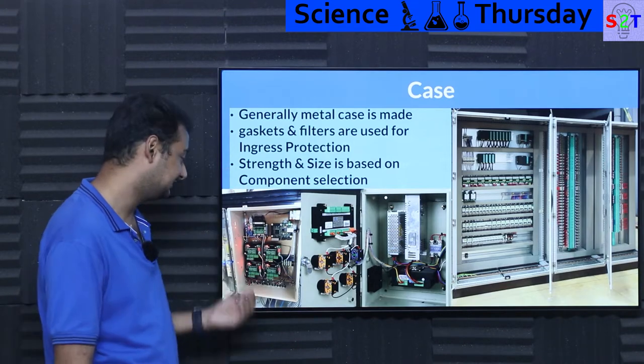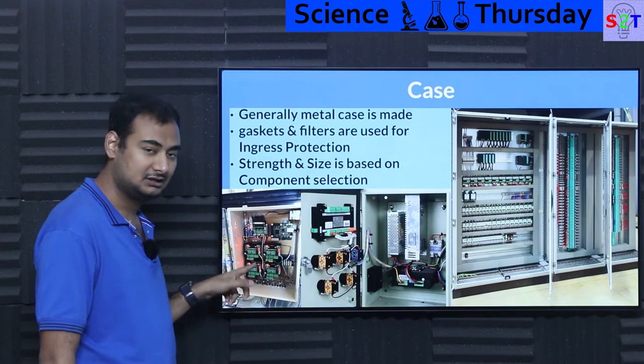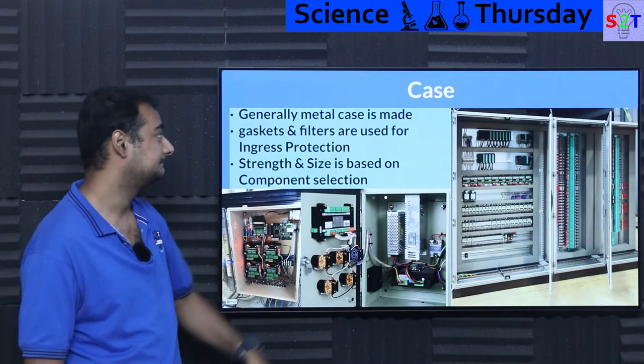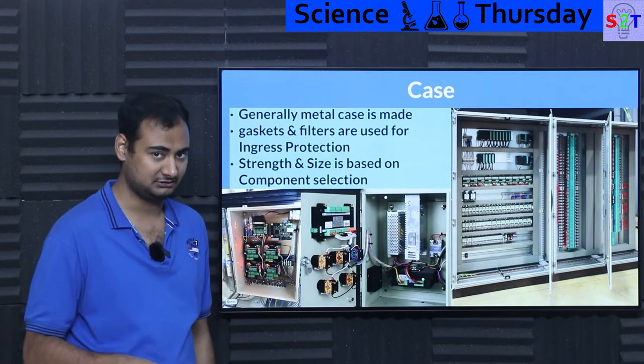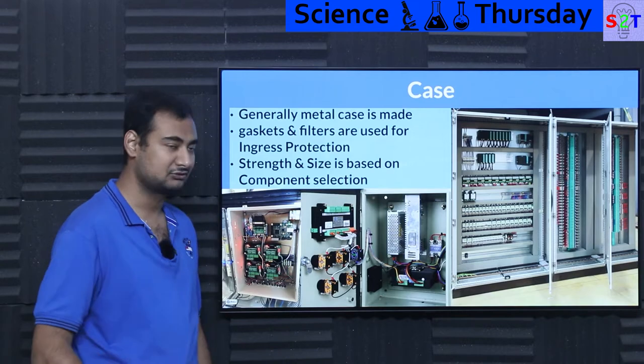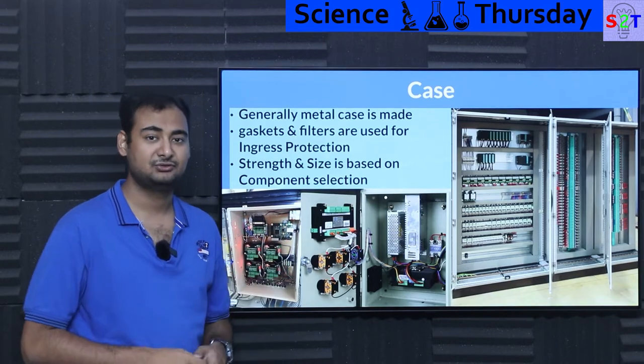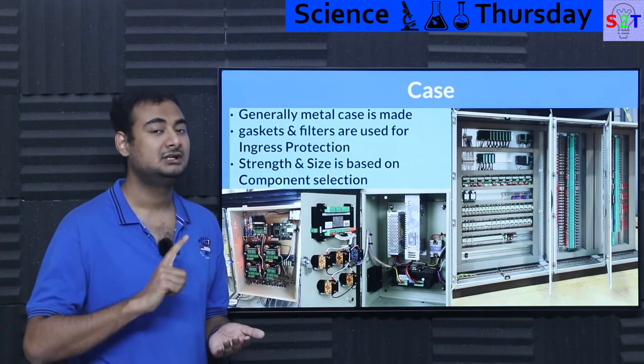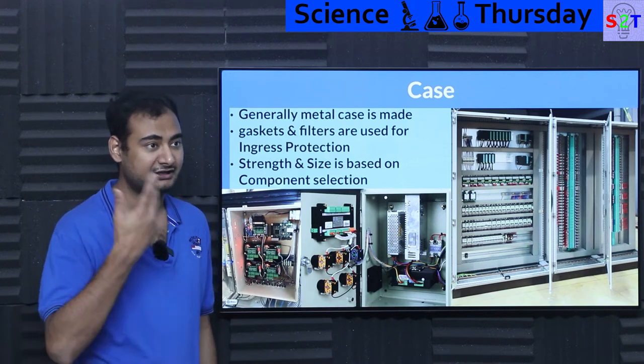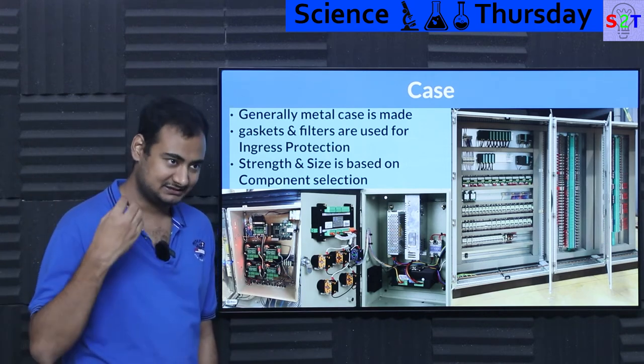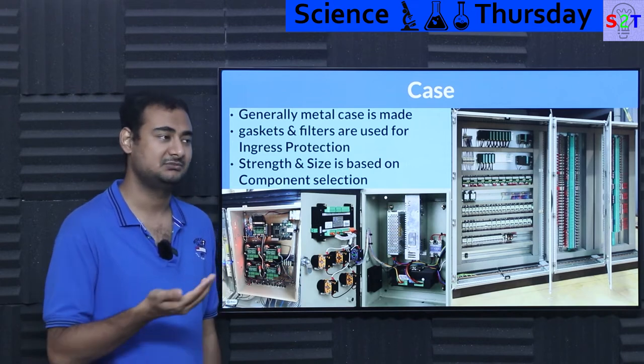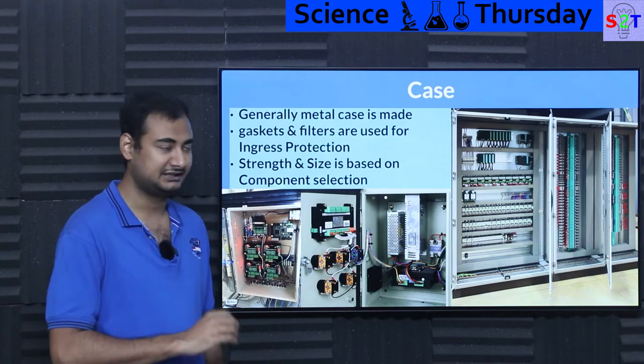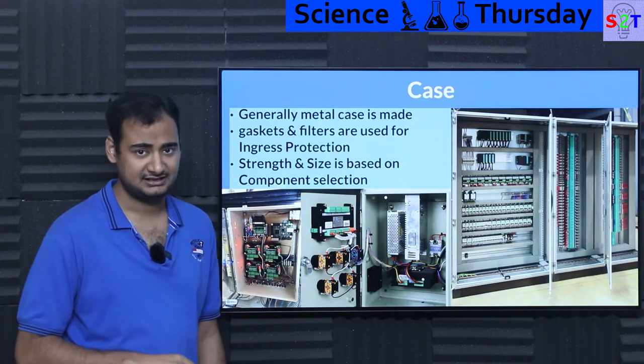Strength and size of the box is based on the components — a small laser cutter will have small things, while something huge requires a large box. Cases must be designed very thoroughly; you cannot just copy-paste. Contactors have coils that generate heat over time — not on day one, but by day 15 or 16 you may find it starting to overheat. Nowadays many boxes have ingress sensors inside that can detect internal temperature, humidity, and other conditions.